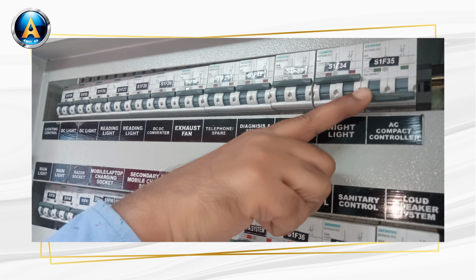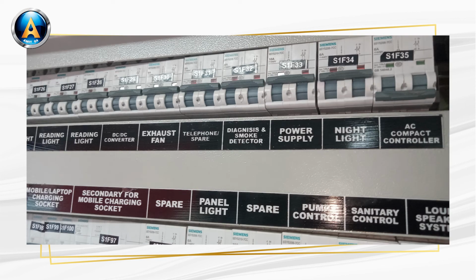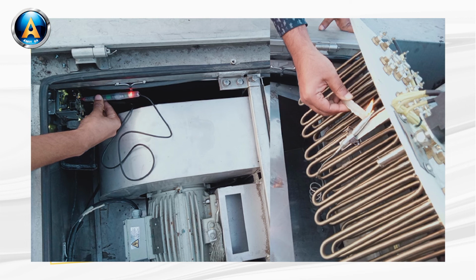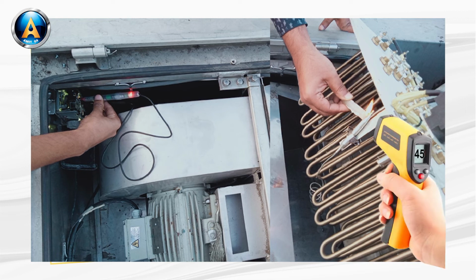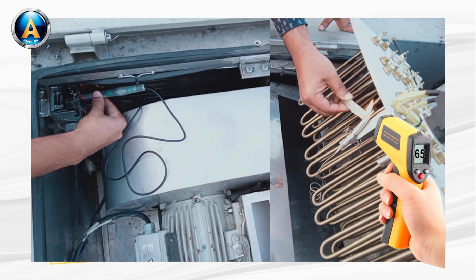After switching off the 110 volt DC power, a continuity tester should be connected with the terminal of the OHP device, and simultaneously the light of the tester should glow. If it glows, then a candle with flame should be brought near the thermal sensor. Whenever the air temperature near the sensor reaches 65 degrees centigrade, then the tester glow should go off. That means OHP OK.